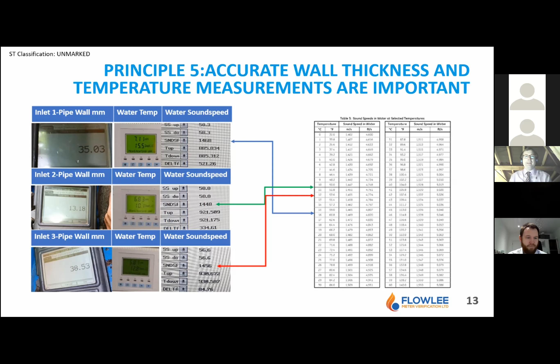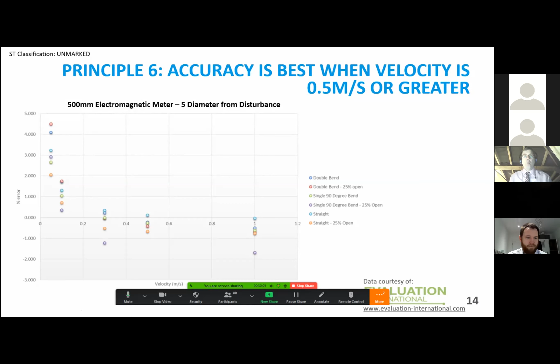Principle 6 is accuracy is best when velocity is ½ meter per second or greater. There's lots of testing that has proven this, and I'm just using an example of an EMAG test that was done up in Scotland with Evaluation International, but I've got similar data for ultrasonics and such like. As you get to a higher velocity, accuracy does improve, but once you get to about 0.5 or thereabouts, the change is really marginal, if anything at all. When you have really, really low velocities, you can get some really big errors. So I would suggest, if I was writing a design manual, I would say you want at least 0.5 meters per second or greater for your velocity.